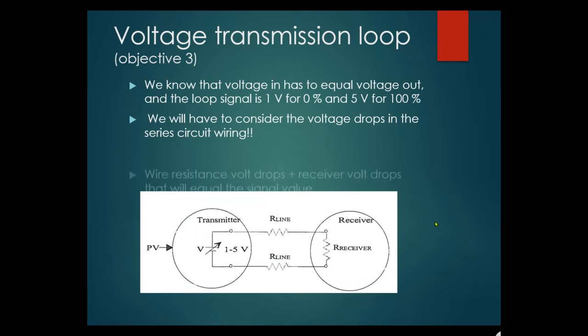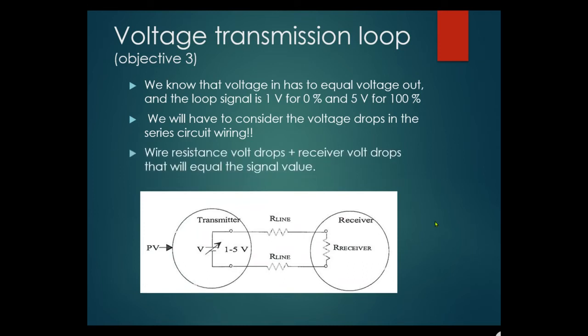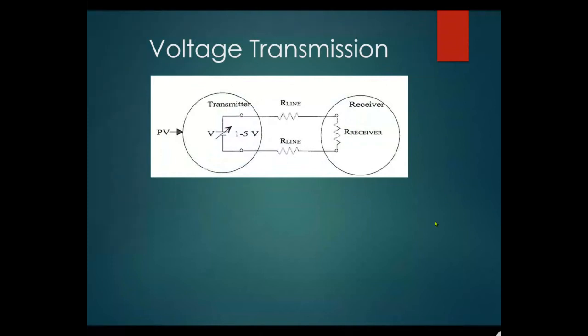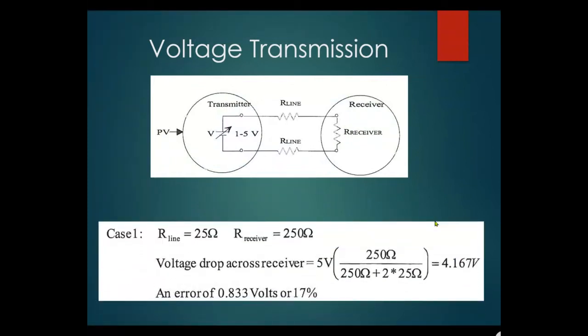In the series circuit, wire resistance voltage drops plus receiver voltage drops must equal the signal value. Case one: line resistance is 25 ohms, receiver is 250 ohms, supply is 5 volts. Voltage drop across the receiver: 250 divided by (250 + 2×25) equals 4.167 volts — I never get to the full 5 volt drop. That's an error of 0.833 volts or 17 percent.